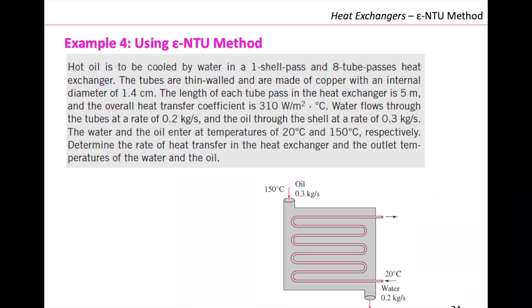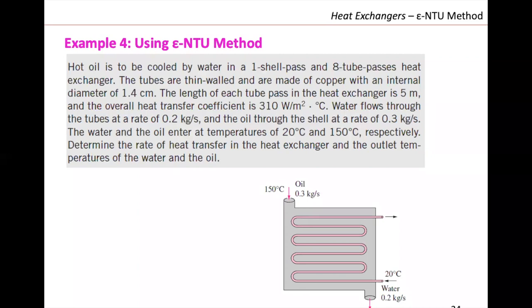We have hot oil that is going to be cooled by water in a one-shell pass, eight tube passes heat exchanger. The tubes are thin-walled and made of copper with an internal diameter of 1.4 centimeters. The length of each tube pass in the heat exchanger is five meters. That is a rational number — last time we were looking at a double pipe of around 100 meters, which was not practical. So we organize in this geometry: five meters with multiple passes. The overall heat transfer coefficient is 310, which simplifies the problem because we don't need to calculate the convective heat transfer coefficients from our forced convection correlations.